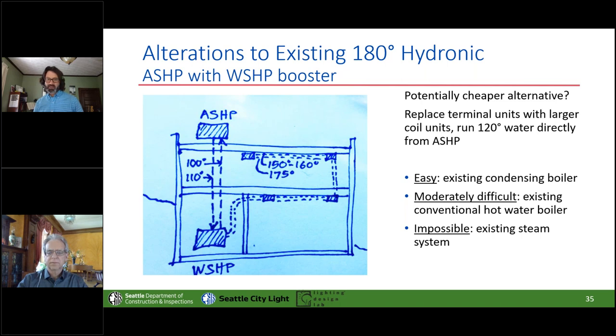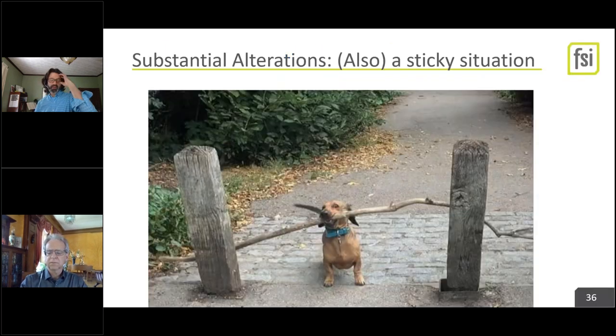So no newer gas, electric resistance heating. That is your margin for substantial alterations, and it will put you in a sticky situation some of the time. So consider, we'll start with impossible and easy. So consider steam boilers. We don't have a way to heat pump to steam, at least not in a commercially available way. It just doesn't get to high enough temperatures. So if you had steam throughout your building, you're going to be looking at replacing most all, if not all, of your system. Then we already did the 180 degree hot water.